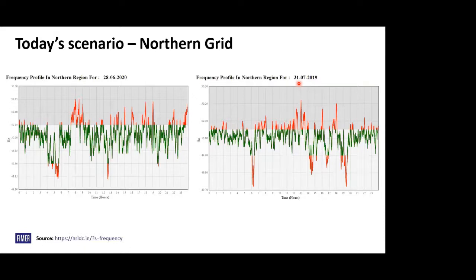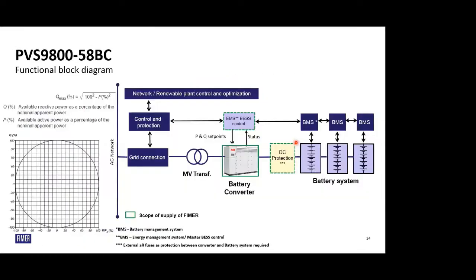So basically this has continued, and it will be an issue going ahead if you do not address it with microgrids. It is like you are just riding on luck, and on some bad day when other factors also line up, you will have problems of grid tripping. This is at the 400 kV level. So how do we address such things? The only answer is utility scale storage solutions, which the CEA can use to address such overloads whenever they happen. They also tell the generating stations to keep 5% reserve capacity. That means don't generate more than 90% or 95% of the generator capacity. Keep that 5% as reserve to address intermittent overloads, whenever at some point some generator or some grid has tripped.